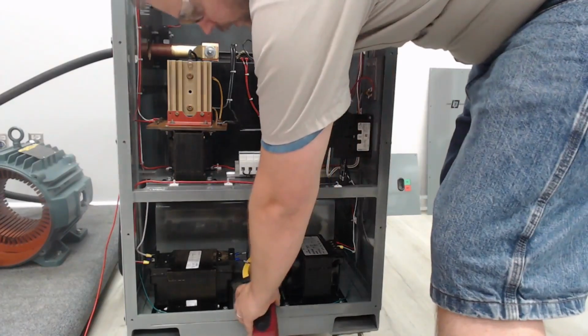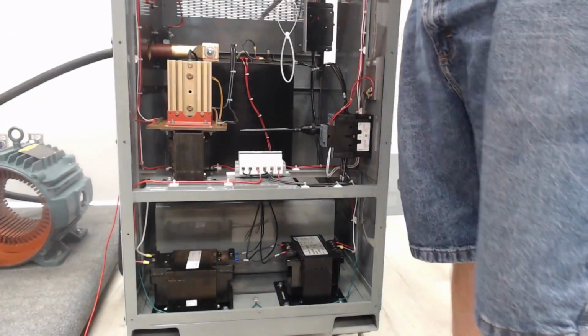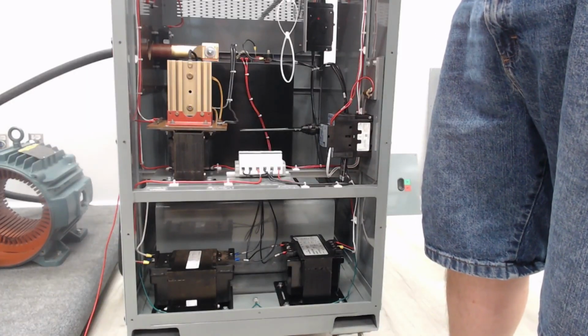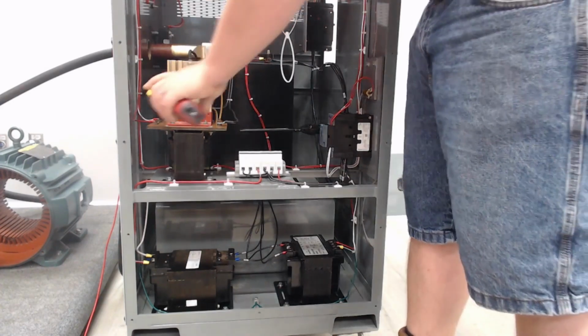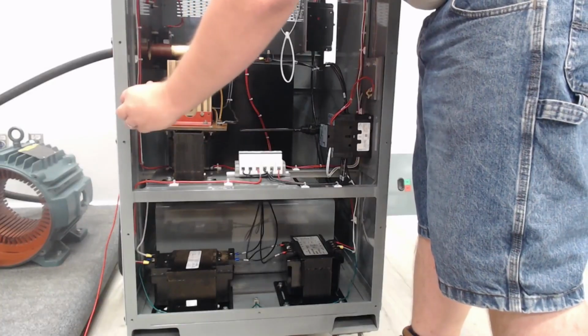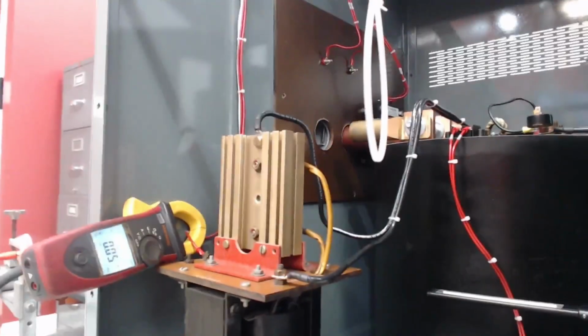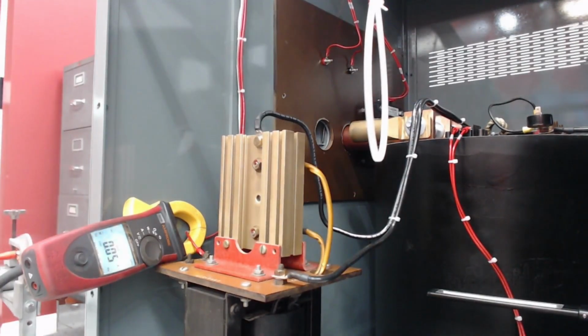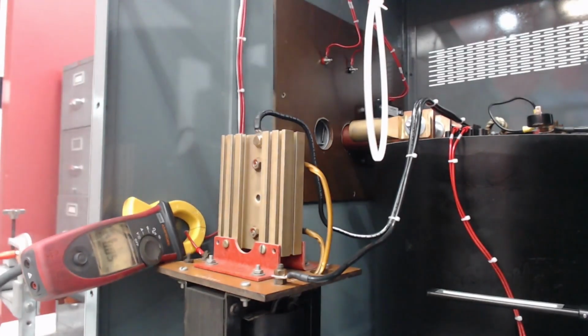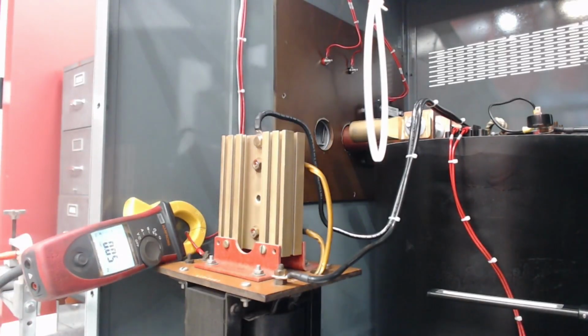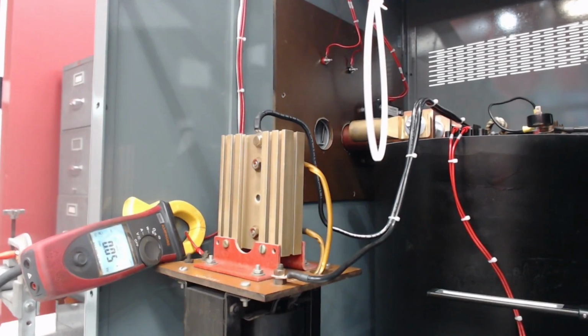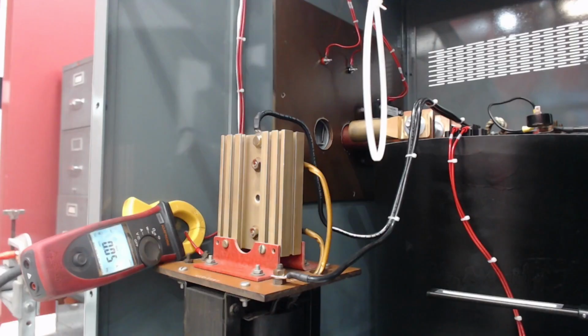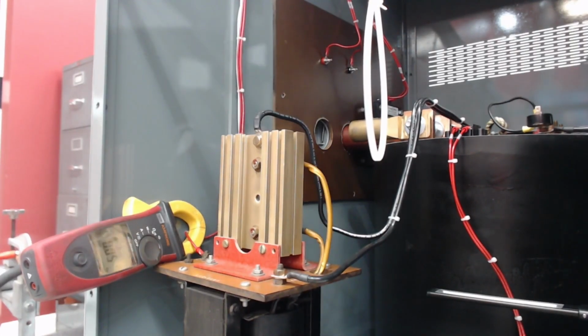The other thing you can check is amperage on units and everything. We want to go ahead and set the meter back to amp and max. I might need to move the camera so I can check right here on the volts. DC power supply. Okay, so right now the unit's off, and the unit will stay off because I'm not turning the unit on. So I'm not getting any readings, because there's no draw. If I was getting anything, then the diodes may be bad, or the 50 amp SSR may be faulty and no longer blocking voltage. And that's why you're blowing fuses: it's letting voltage through, and the unit's not basically starting at a 0 point. It's starting with an actual load.